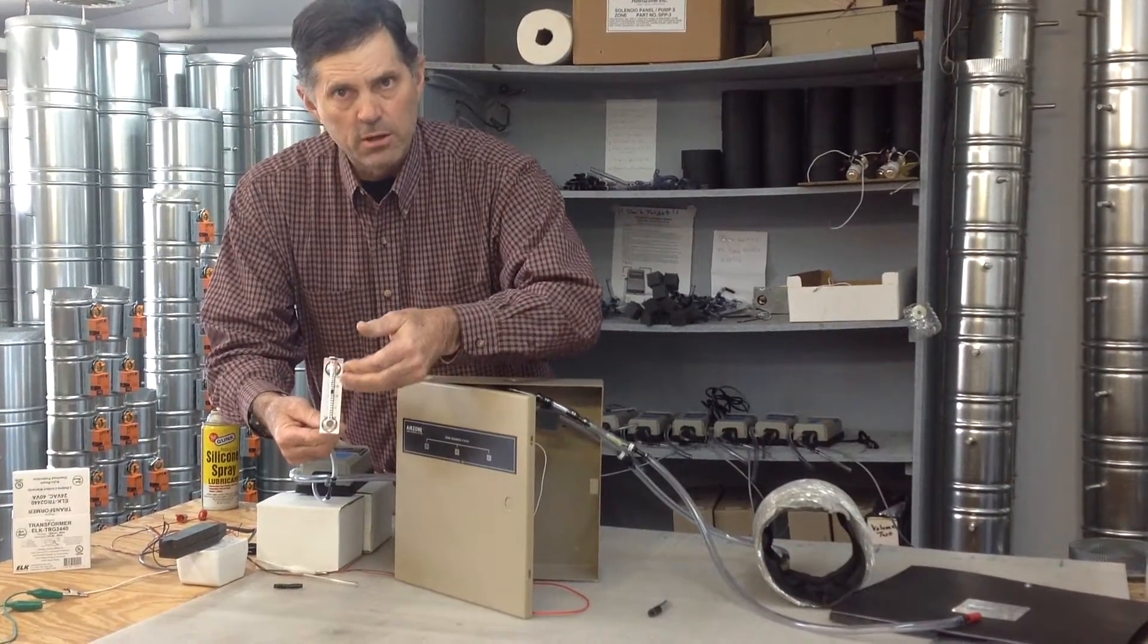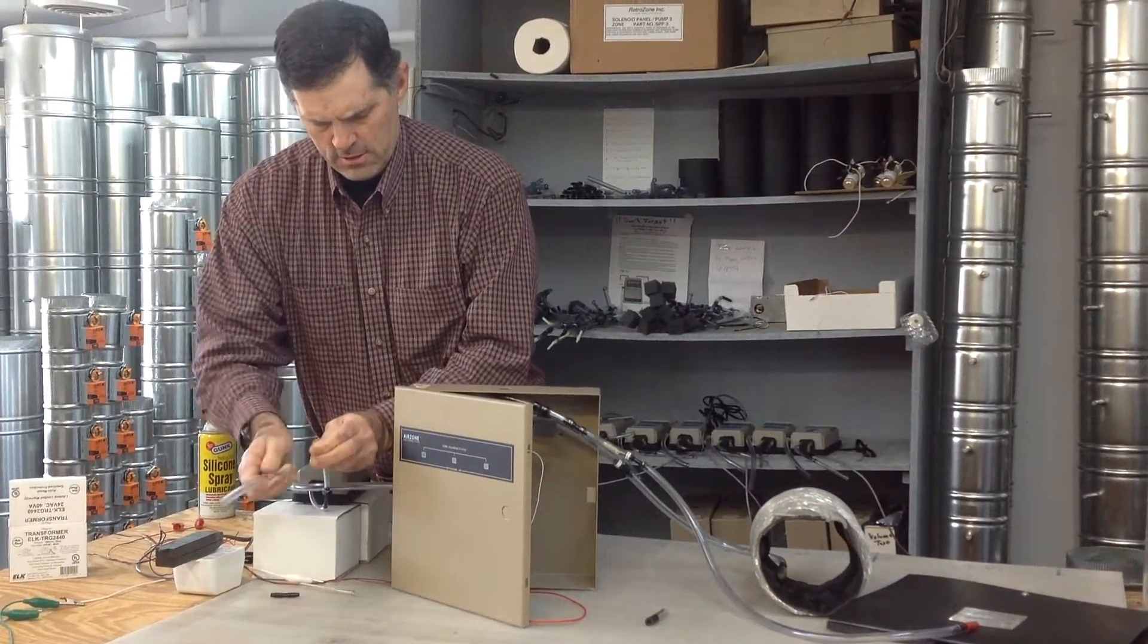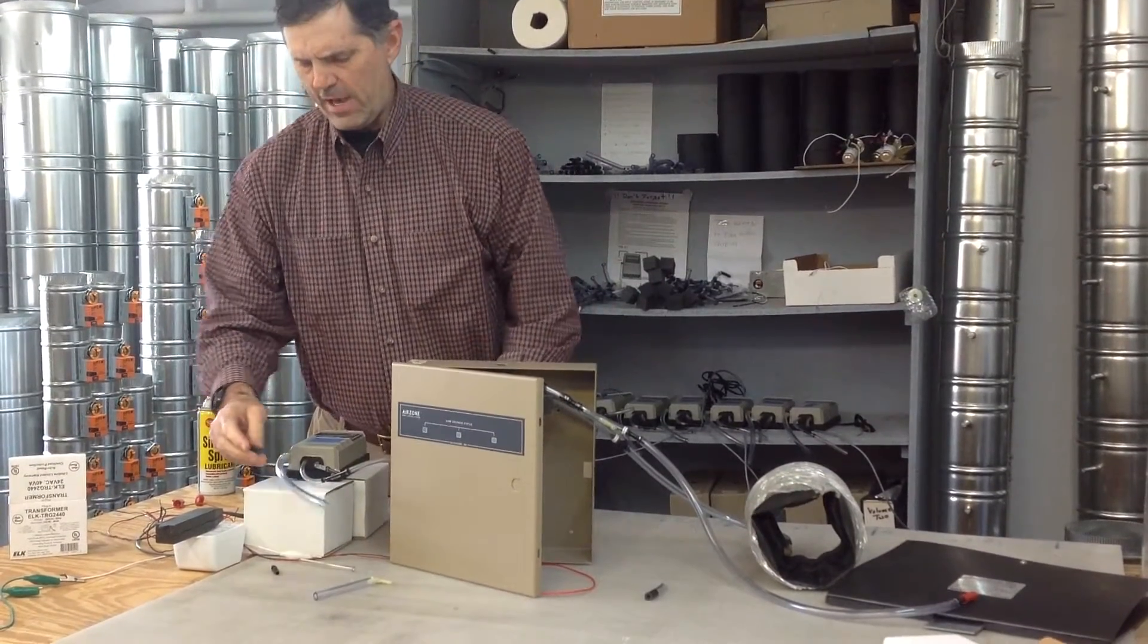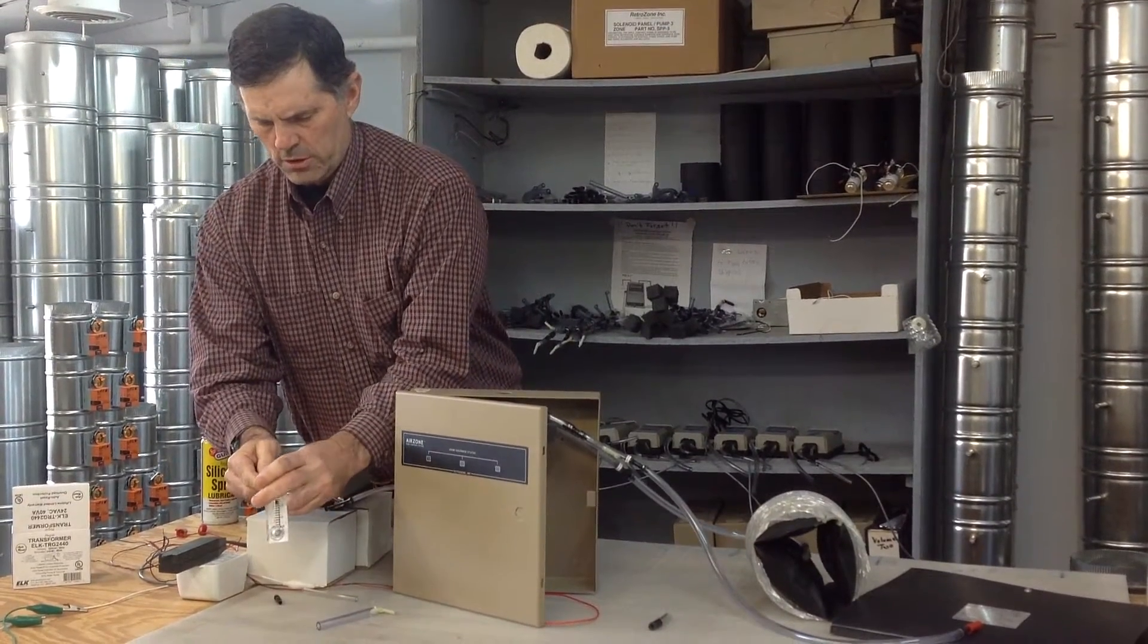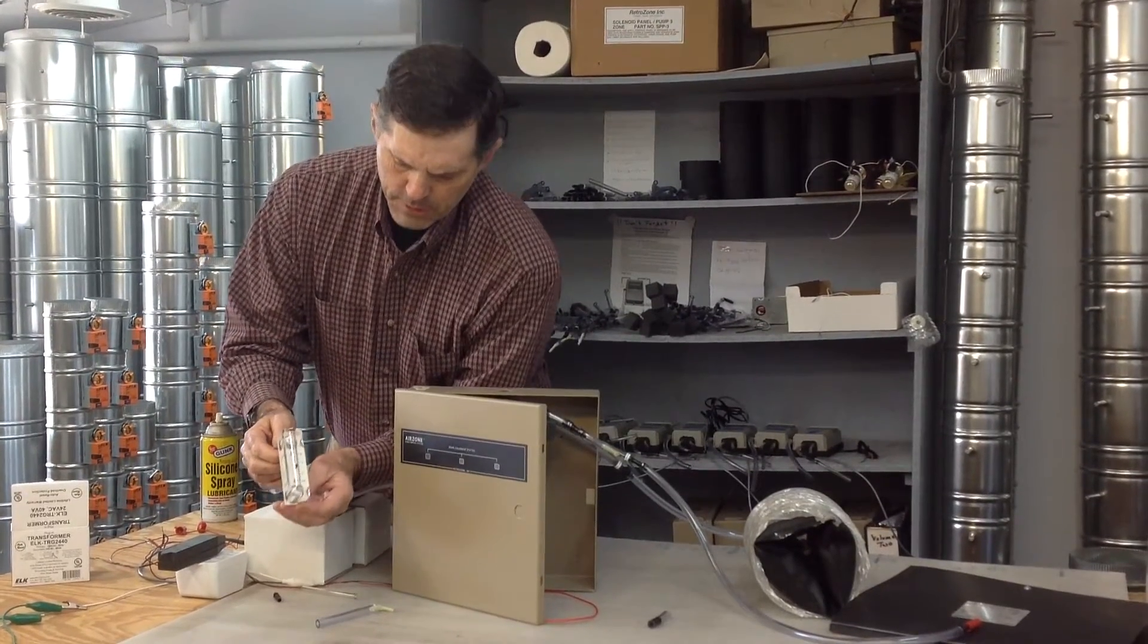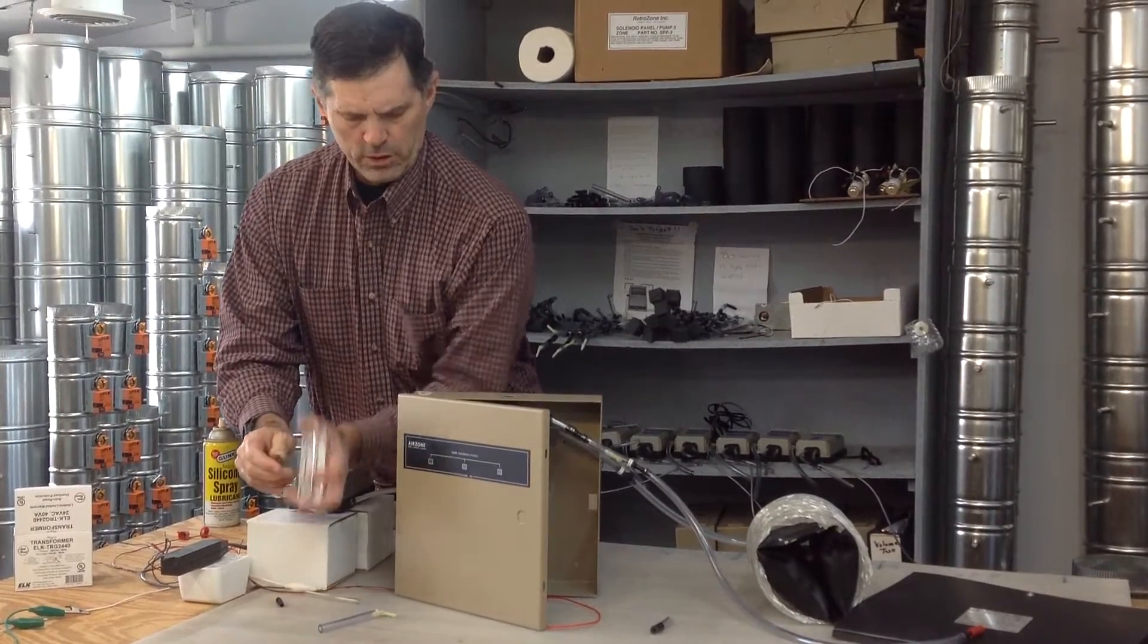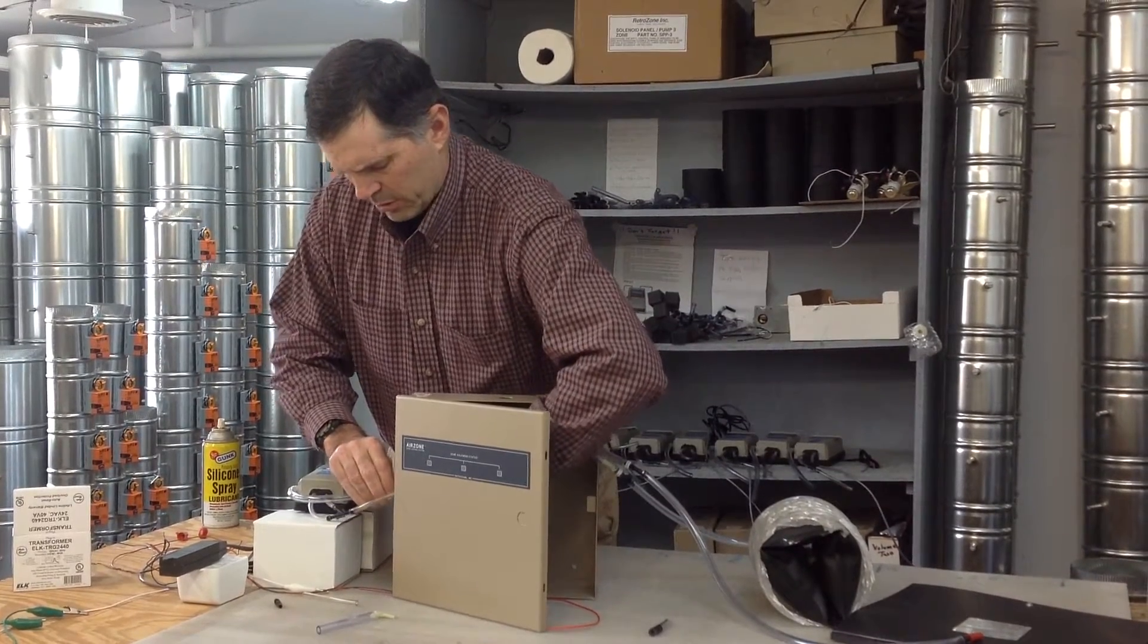Can we actually see the ball in there? Okay, good. Now, we're going to reconnect that. We're going to disconnect the vacuum side and test it. Same way, the vacuum side is actually the bigger tube going into the side of the pump. For this, we want to use the top port. Once again, I think you can see the ball picking up. It's running about 10 or 12, also a very good number. Anywhere around 5 or better on the vacuum side is a good number. We've now verified that pump. You know it's a good pump.